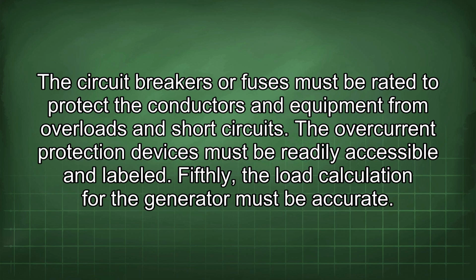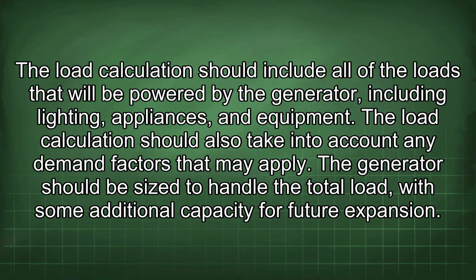Fifthly, the load calculation for the generator must be accurate. The load calculation should include all of the loads that will be powered by the generator, including lighting, appliances, and equipment. The load calculation should also take into account any demand factors that may apply. The generator should be sized to handle the total load, with some additional capacity for future expansion.